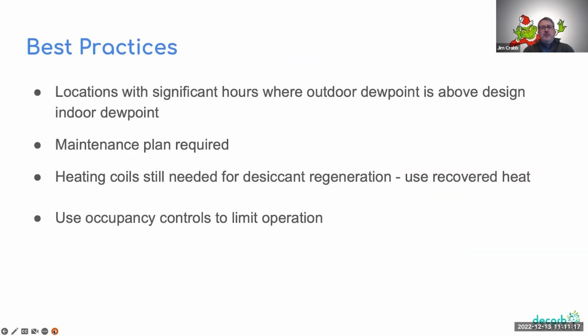So when we do this, what we're talking about is using that desiccant to remove moisture from the outside air. We would do that primarily in places where there's a significant number of hours where the dew point's above our design. Again, in a good bit of California, that might apply to ORs, but it probably wouldn't apply to general areas. This is a rotating wheel. It rotates through the airstream and then through the reactivation air. So there is some maintenance involved.